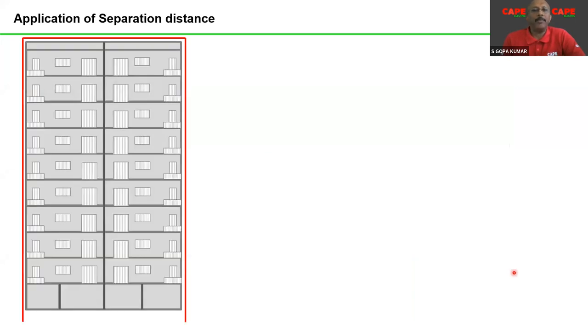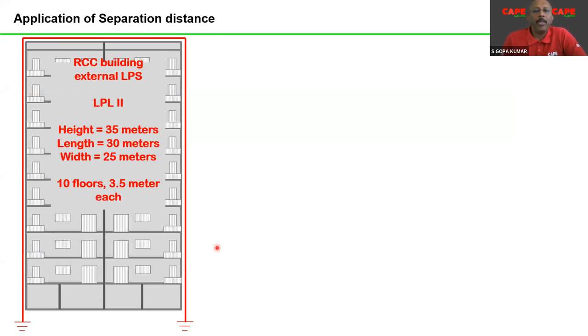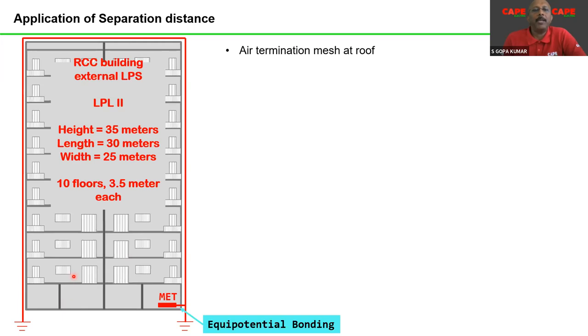With those standards, I'm just trying to find out the separation distance in an RCC building where I'm going to make an external lightning protection system, a level 2 lightning protection. The height of my building is 35 meters, length 30 meters, width 25 meters. Just as an example, think that it's a 10-floor building, 3.5 meters each. I wanted to make an external lightning protection system with the equipotential bonding at the bottom. I'm trying to find out the separation distance.